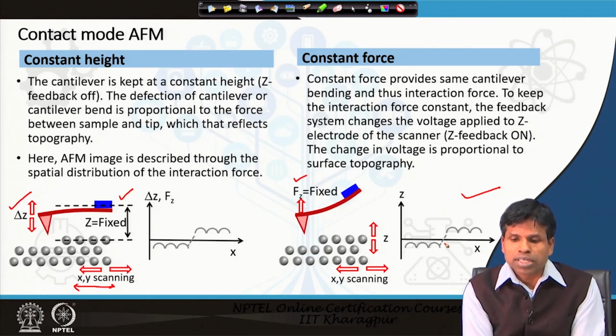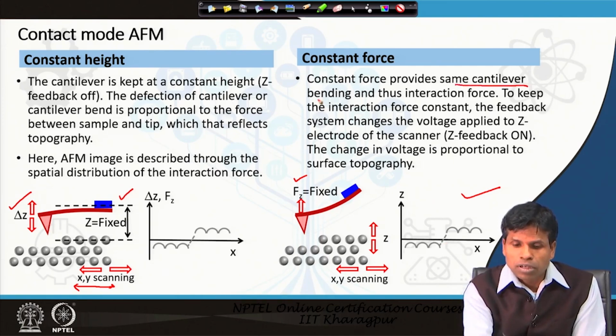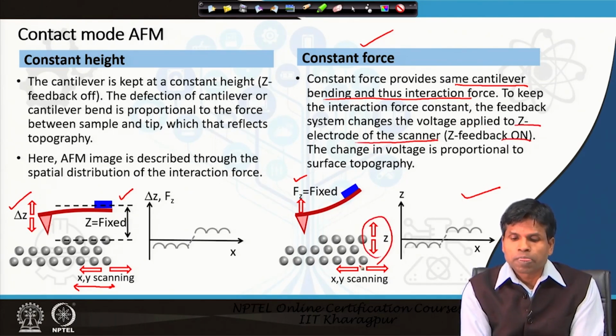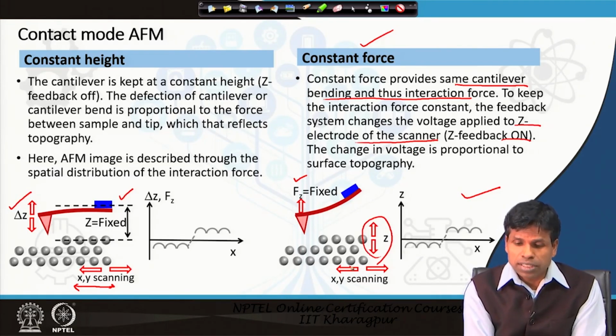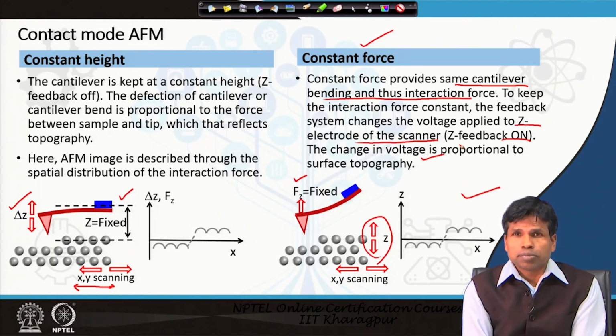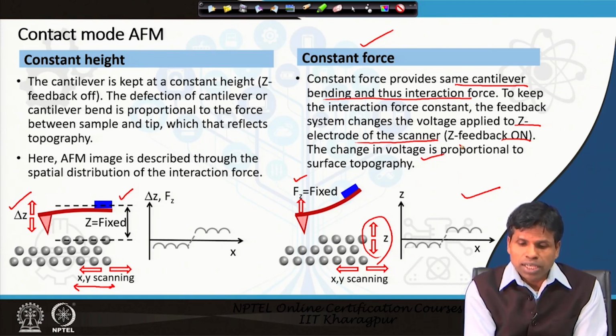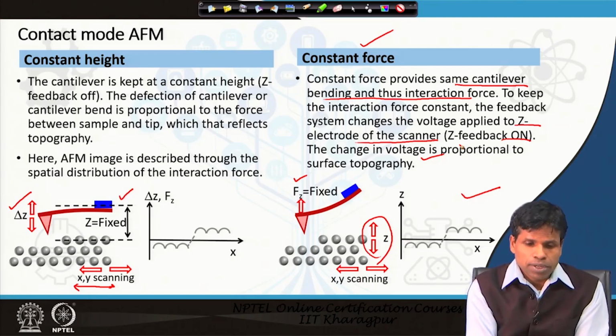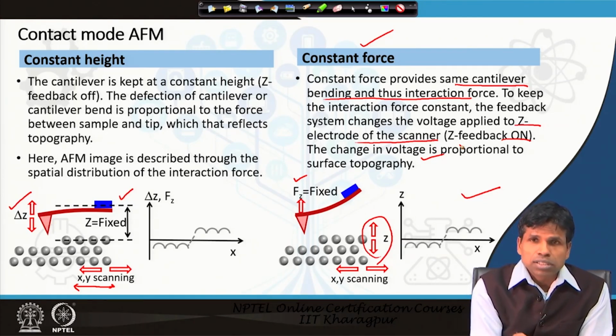So, constant force mode provides the same cantilever bending, that is the interaction force, which is kept constant, that is why it is called constant force. And to keep the interaction force constant, the feedback system changes the voltage applied to the z scanner. So z feedback is on here, and the feedback is given with piezo materials on the sample stage, and the change in voltage is proportional to the substrate surface topography. In this way, we can measure the surface topography or 3D image of the sample by using constant force mode. So both processes give us the same 3D image.